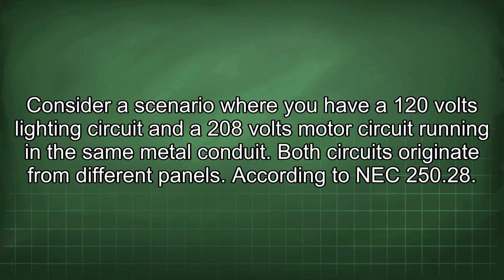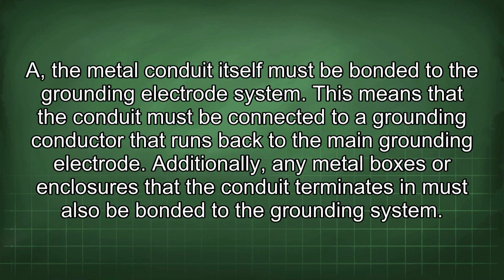Consider a scenario where you have a 120 volts lighting circuit and a 208 volts motor circuit running in the same metal conduit. Both circuits originate from different panels. According to NEC 250.28(A), the metal conduit itself must be bonded to the grounding electrode system. This means that the conduit must be connected to a grounding conductor that runs back to the main grounding electrode. Additionally, any metal boxes or enclosures that the conduit terminates in must also be bonded to the grounding system.